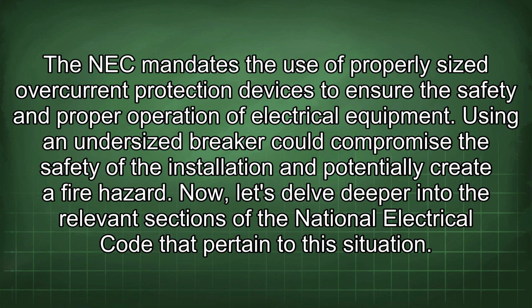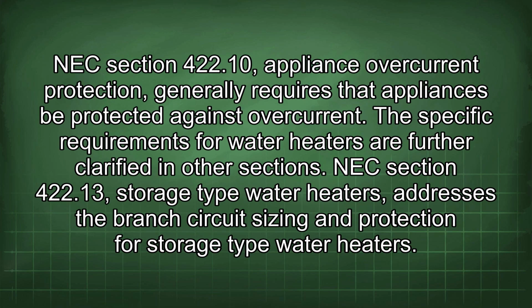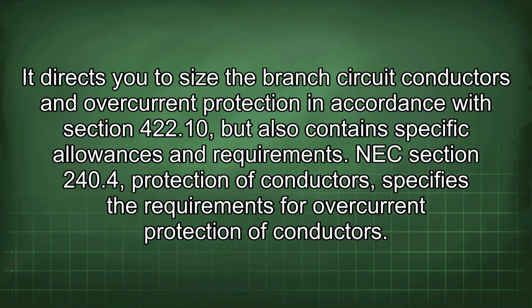Now, let's delve deeper into the relevant sections of the National Electrical Code that pertain to this situation. NEC Section 422.10, Appliance Overcurrent Protection, generally requires that appliances be protected against overcurrent. The specific requirements for water heaters are further clarified in other sections. NEC Section 422.13, Storage Type Water Heaters, addresses the branch circuit sizing and protection for storage type water heaters.